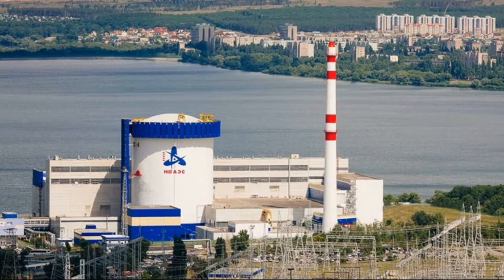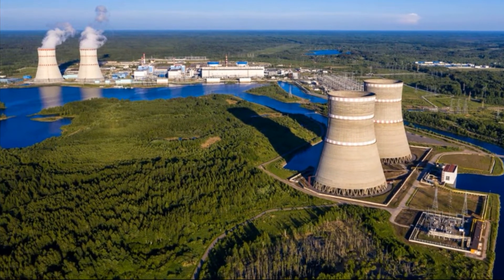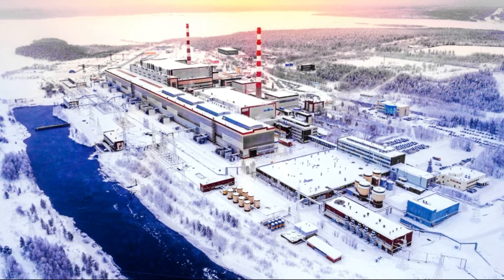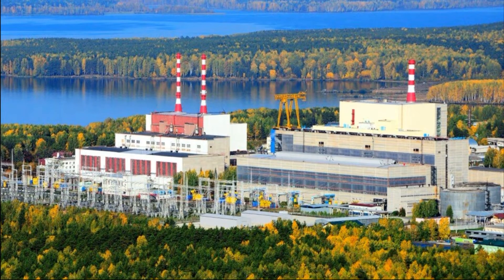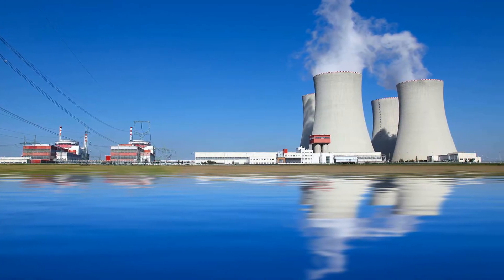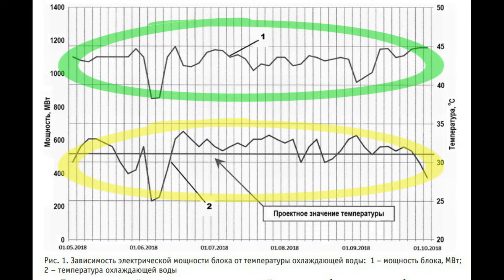For the normal operation of a nuclear power plant, the temperature of the cooling water can vary within fairly wide limits — the lower, the better the cooling will be efficient. But even in the heat, technically, nuclear power plants can work. It's just that if the water is above a certain value, the station will work less efficiently. For example, on this graph you can see the dependence of the power of the first unit of the Novovoronezh NPP-2 on the temperature of the water cooling the condenser. The normal cooling water temperature range is below plus 31 degrees. When it rises higher, the power of the unit decreases.